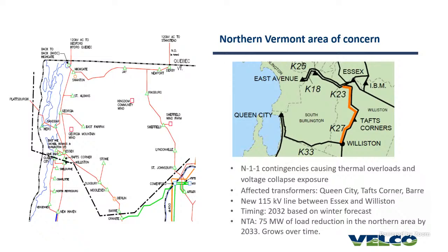This is the northern Vermont area of concern, and what you see are the main issues identified. N-1-1 contingencies, which is what Shana mentioned, losing one line or one generator and then losing another line, that combination caused thermal overloads and possibly some voltage collapse. The transformers affected are at Queen City, Taft Corners, and Barre, which you can see on the map.